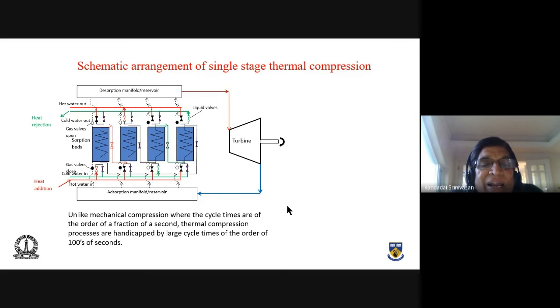They take a few hundred seconds to complete one cycle. So if you want continuous flow, since it discharges only once in about 100 seconds, you need 4 compressors put in tandem - one adsorbing, one heating, one desorbing and discharging, one cooling. This whole cycle takes a few hundred seconds, so you can't have just one, you need 4. That's actually one of the liabilities.